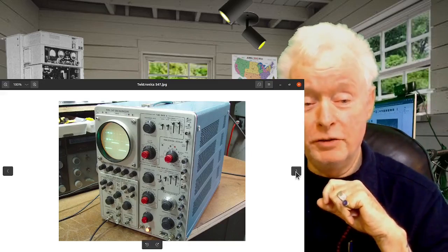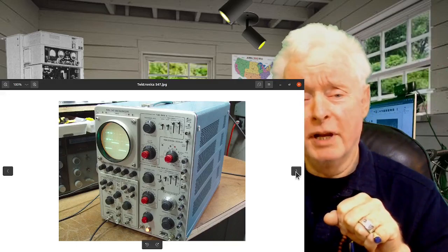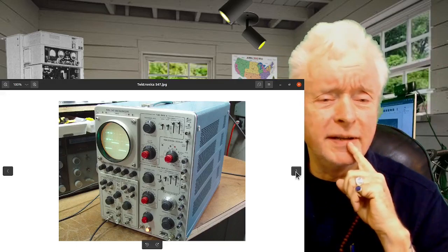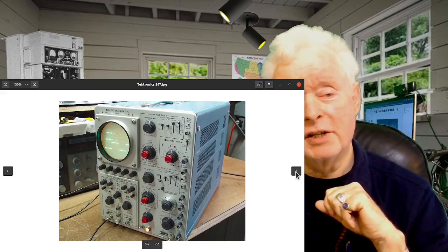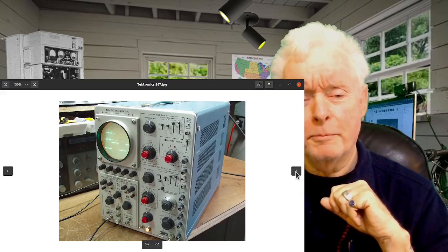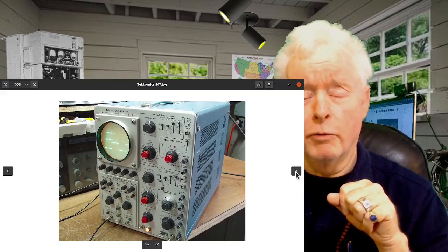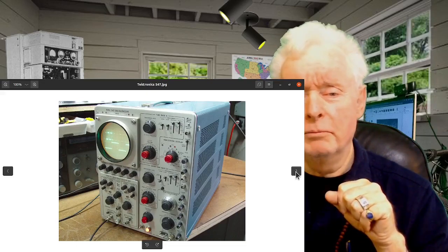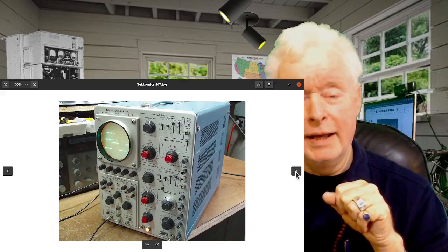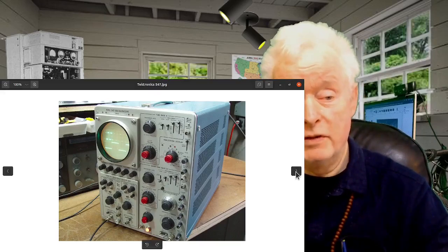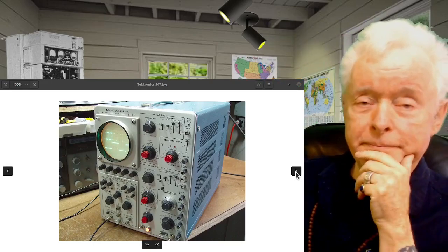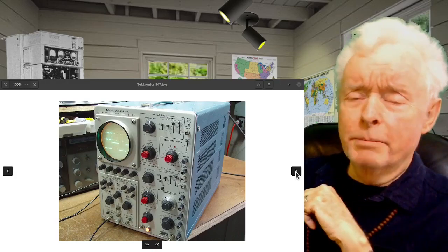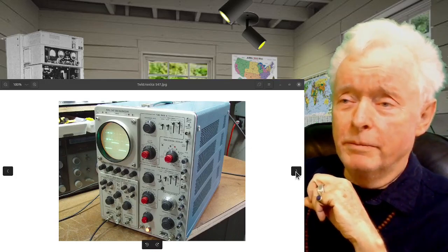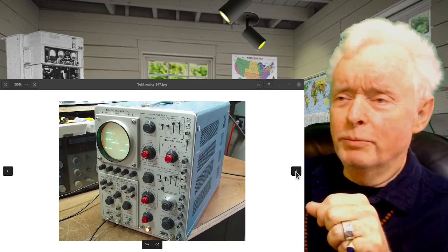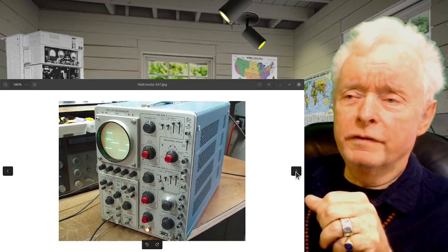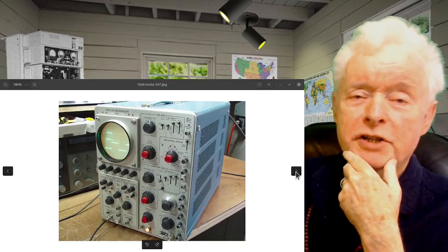This is a workhorse. This too is well, it depends on the plug-in, but it's 100 megahertz. Well, let's see. I haven't checked these specs in a long time. Now, it is dependent upon the plug-in that you see at the lower left. This is a great oscilloscope, and it's full of tubes, certainly. The time to calibrate it is longer than the other, and consequently is probably going to be about a 10% instrument if it doesn't have a current valid calibration sticker on it.